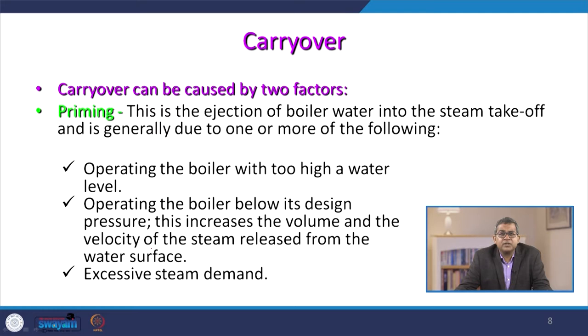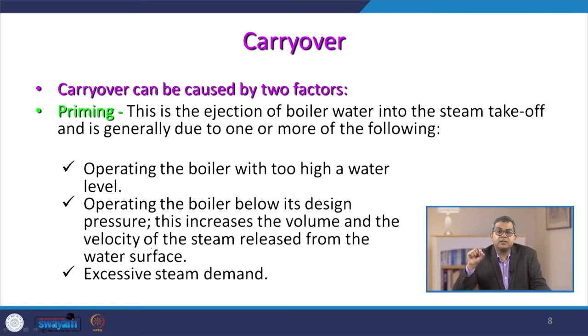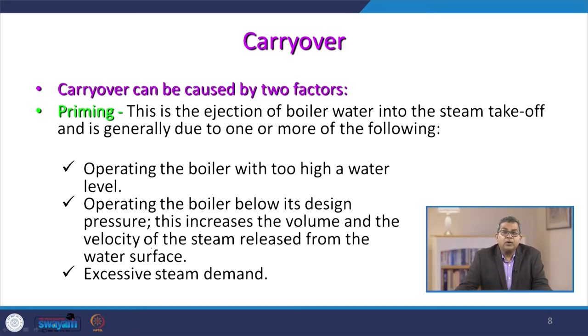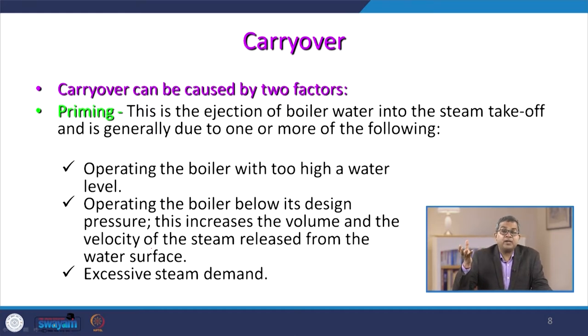Carryover can be caused by two factors. One is priming — the ejection of boiler water into the steam takeoff — which is generally due to one or more reasons: operating the boiler with too high a water level, which is dangerous as it imparts excess energy; operating the boiler below the design pressure, which increases the volume and velocity of steam released from the water surface; and sometimes excessive steam demand.